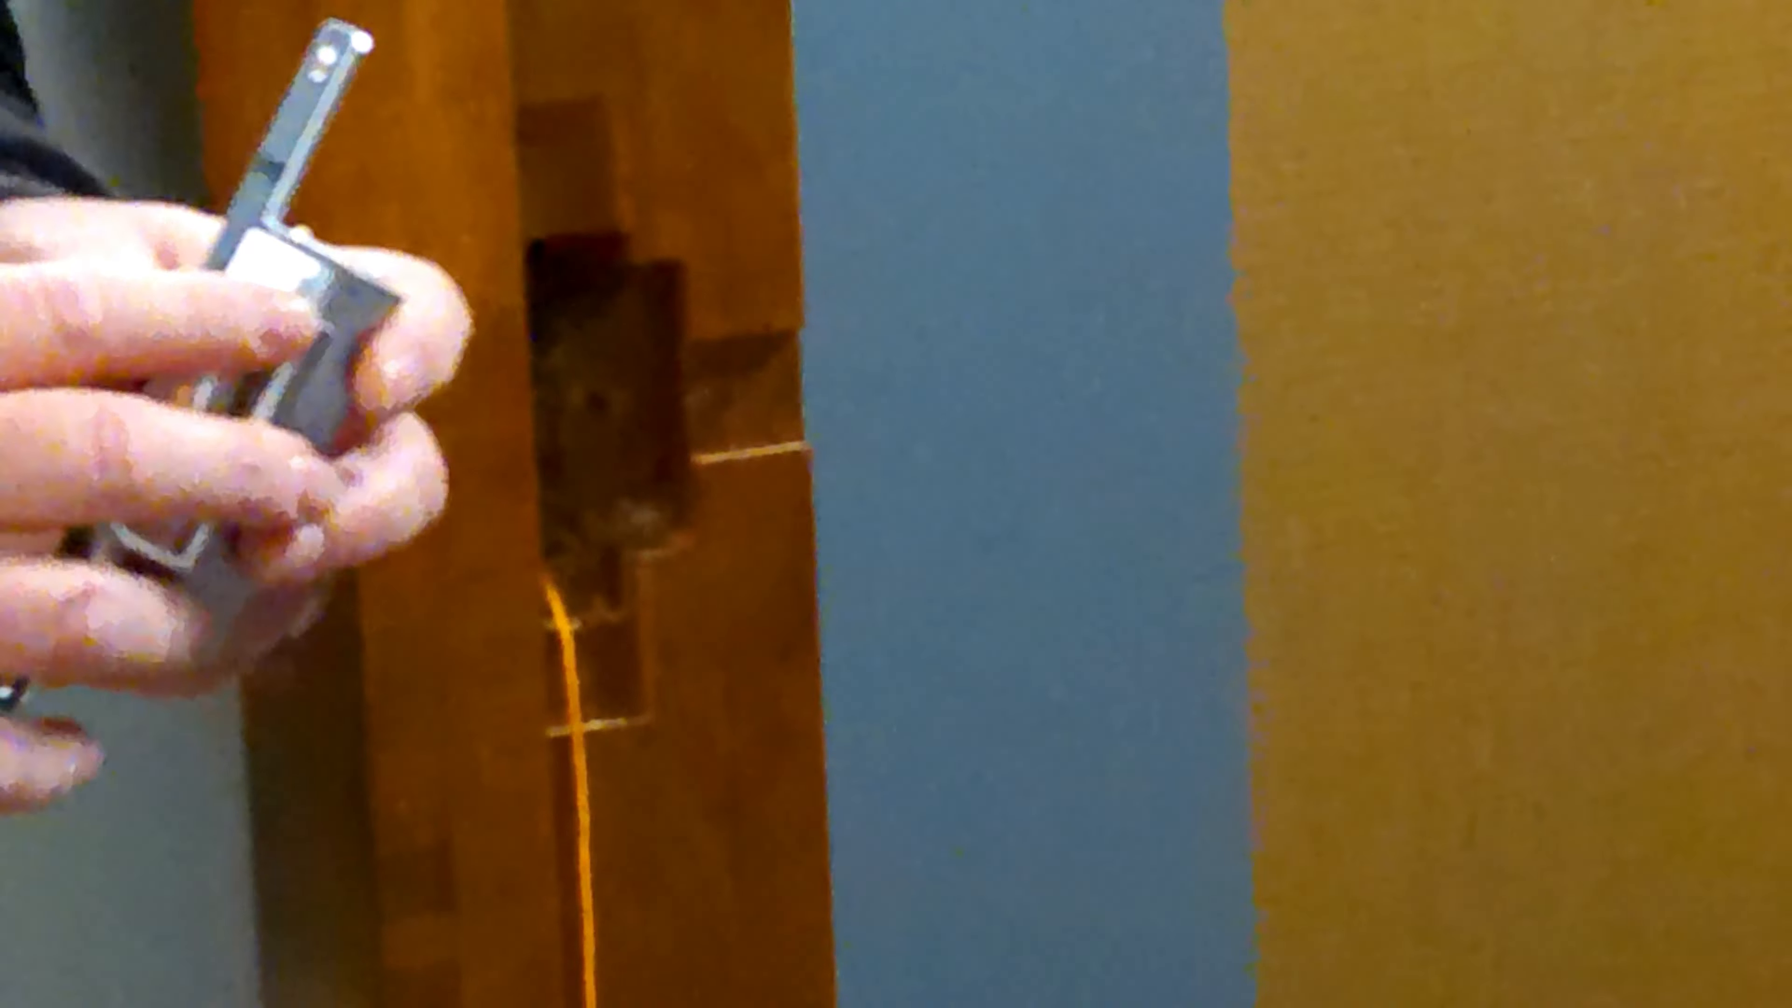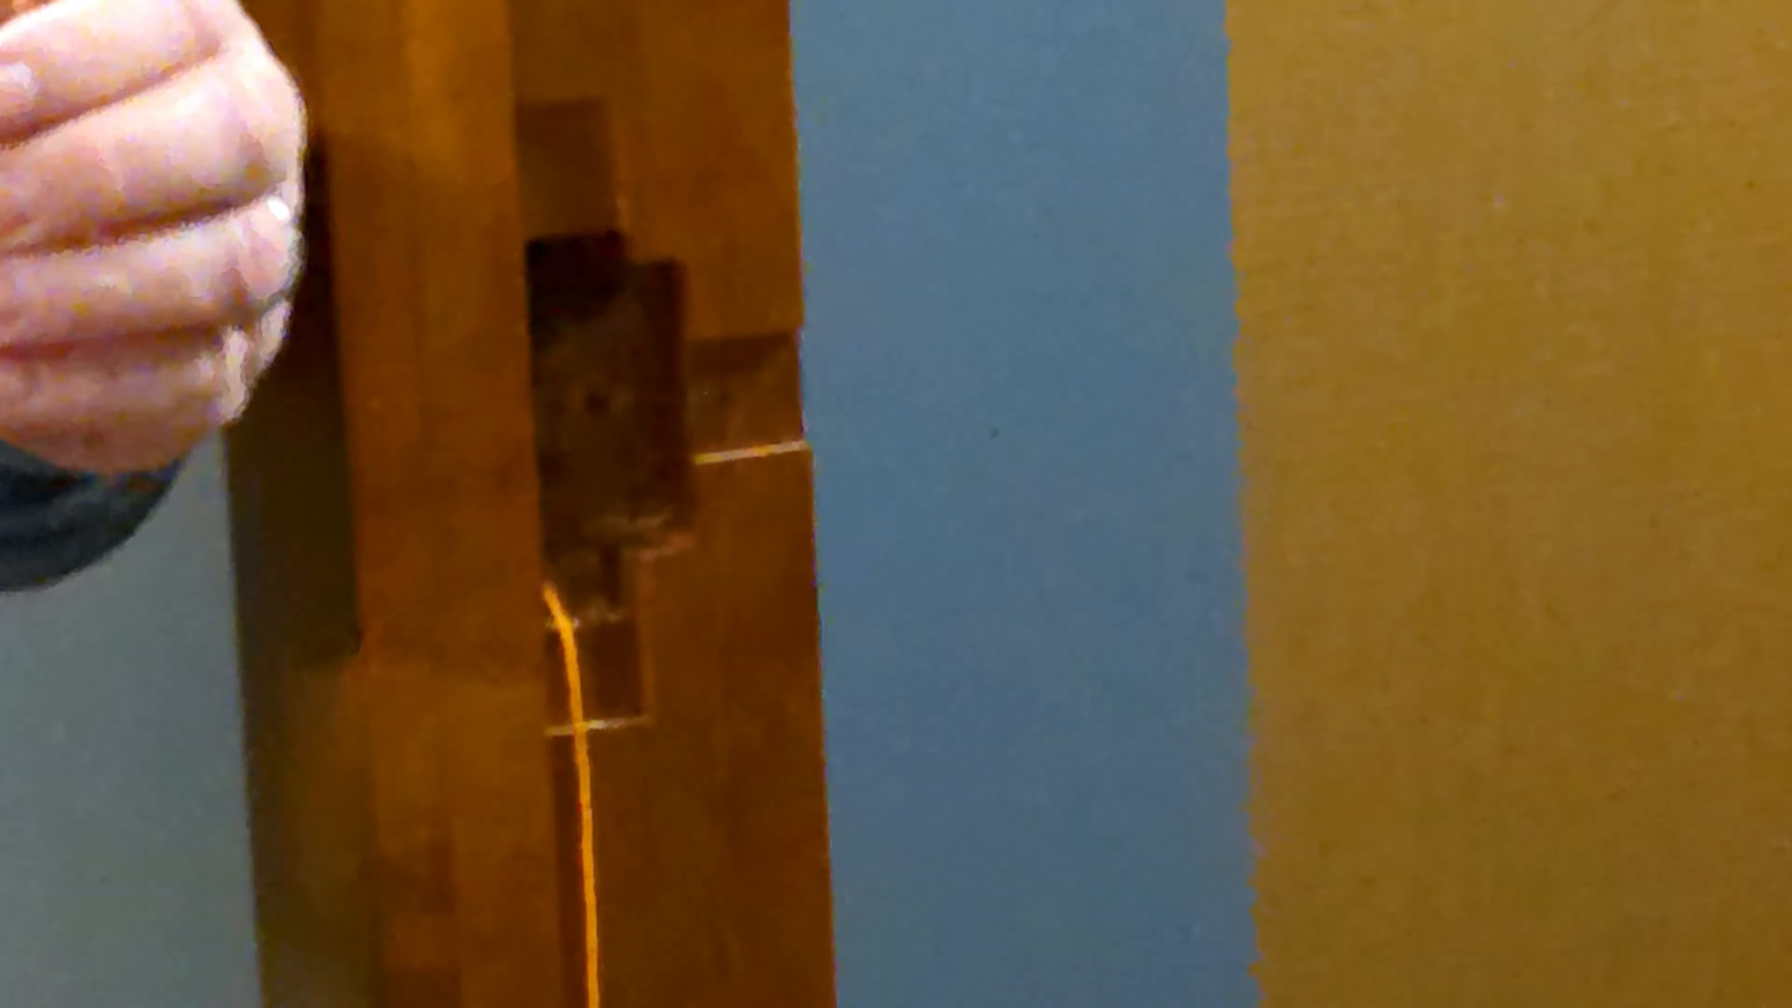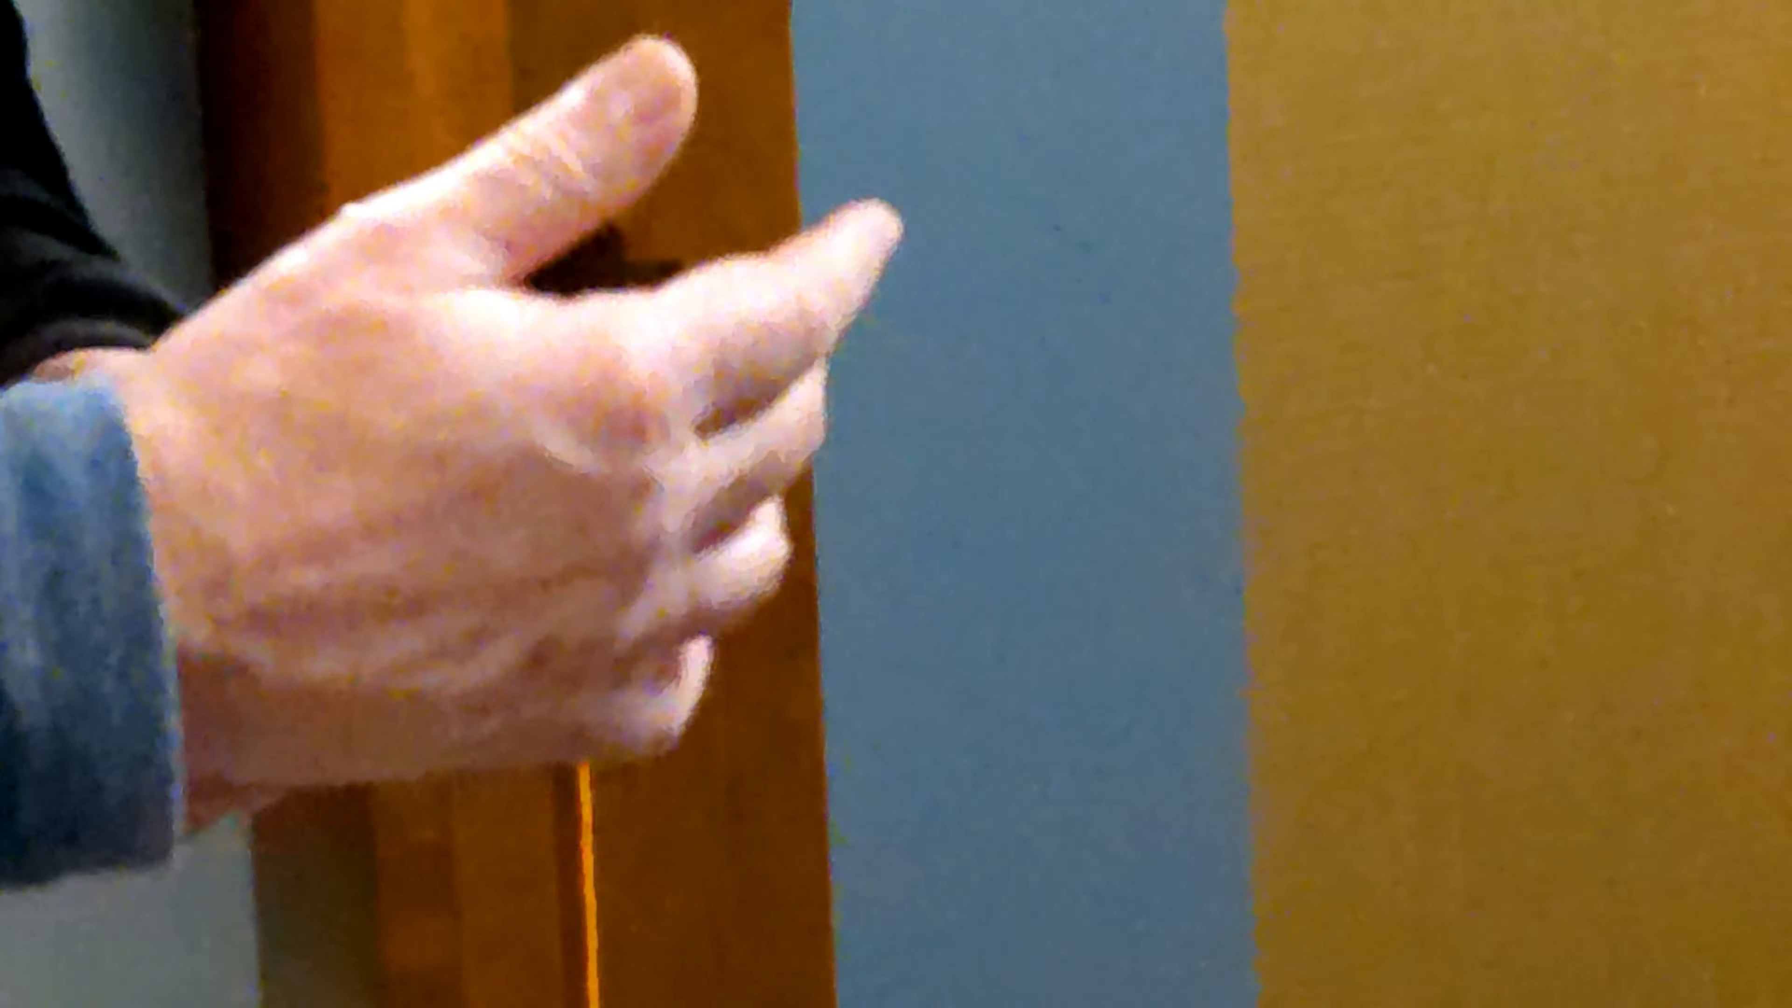When you get your door ready to go in your opening, what you want to do is slide it in your opening and then take a pencil and trace out the inside of this opening onto the stud that's behind here. The reason for that is the depth of the electronic strikes sit a little bit past the jamb, so it wouldn't allow you to put the door in with this in there. You take your door back out and where you traced, you take a chisel and chisel out the back of the 2x4 so it will have enough space for this body of this lock to fit into.